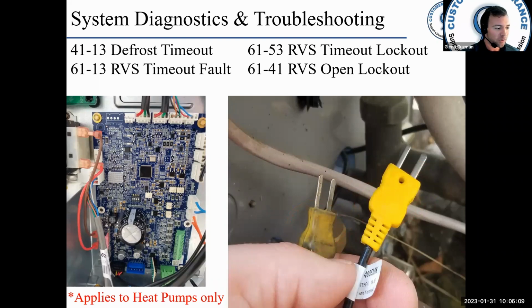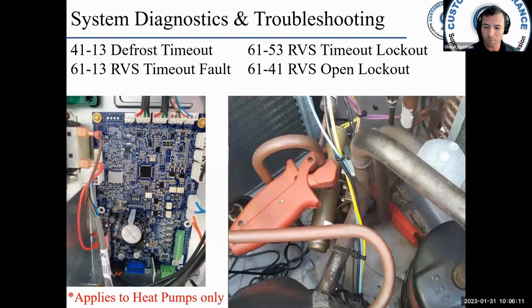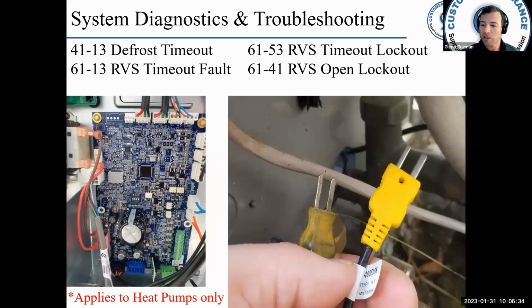Now, what I would do periodically is take my temperature clamp, clamp it onto a piece of ice, and stick it into a cup with ice water, and then look at my meter and see, does it read 32 degrees? It should be at 32 degrees at sea level, which we are at. If I'm testing my meters regularly and I am confident they are reading properly, then I've got no problem using a new and old meter because I am testing it regularly and I make sure it works.